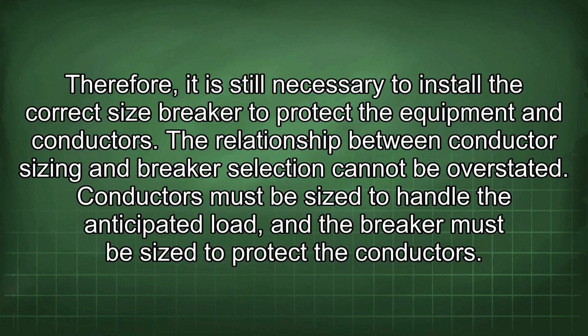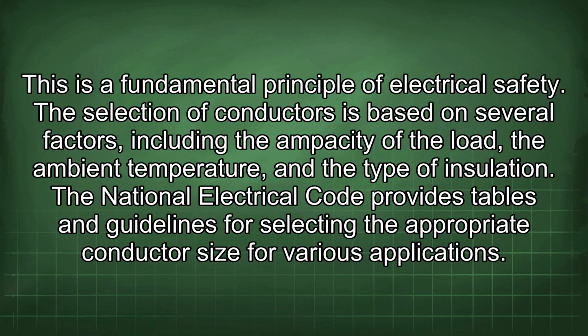The relationship between conductor sizing and breaker selection cannot be overstated. Conductors must be sized to handle the anticipated load, and the breaker must be sized to protect the conductors. This is a fundamental principle of electrical safety. The selection of conductors is based on several factors, including the ampacity of the load, the ambient temperature, and the type of insulation. The National Electrical Code provides tables and guidelines for selecting the appropriate conductor size for various applications.